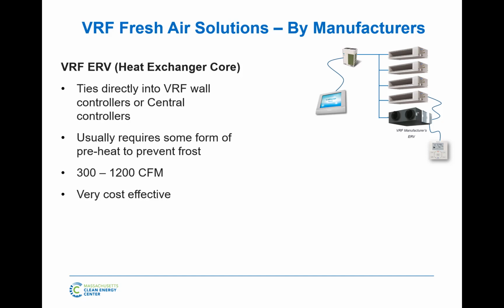The disadvantage is that, well, they only go up to about 1,200 CFM, so that's pretty small. And B, these guys need a little bit of preheat, just to ensure we don't have any frost on the core, the way they're designed. So you need to consider some preheat in the building, especially if your fresh air is humidified. So these are quite common. These are not your multi-res residential 80 CFM ERVs that you put in each condo suite. These start at 300, so they don't go down that small. But that is an option here.